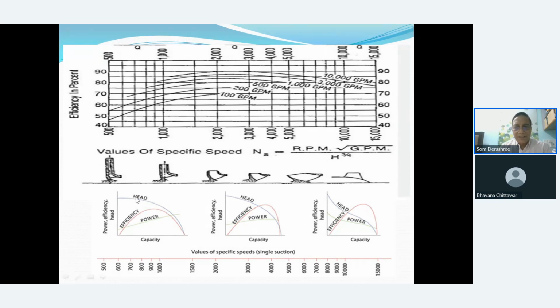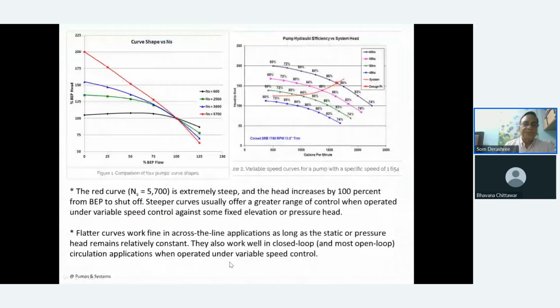You see the head curves are getting flattened out. Efficiency curves are moving slightly, so as you move forward, the efficiency is at a very high capacity compared to the radial efficiency. At this point, radial is maximum, but at this point, this mixed may not be; the mix will be slightly here. And if you talk of the axial, the efficiency will be highest maybe at very, very high flow. Head may not be that high in requirements.